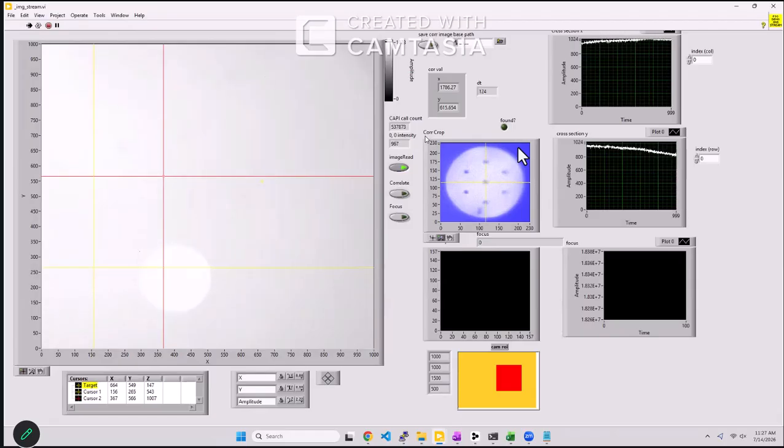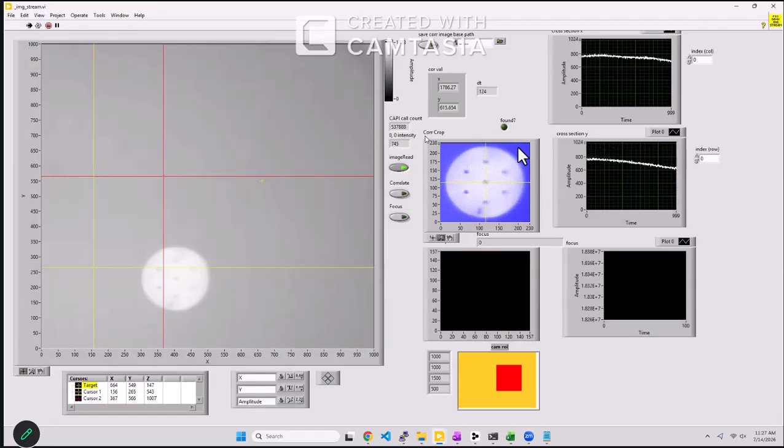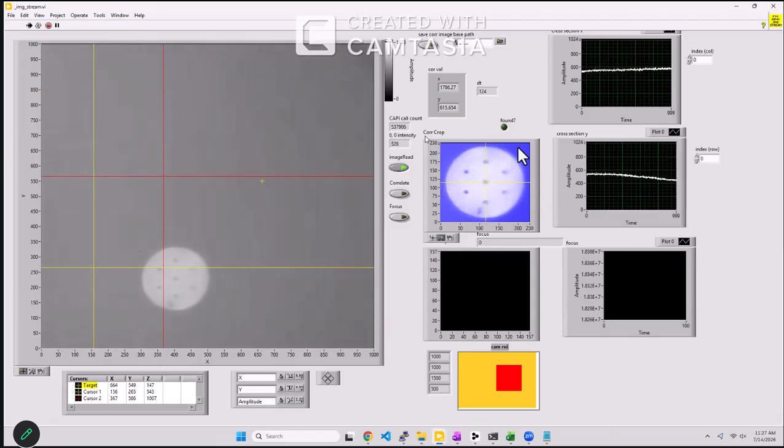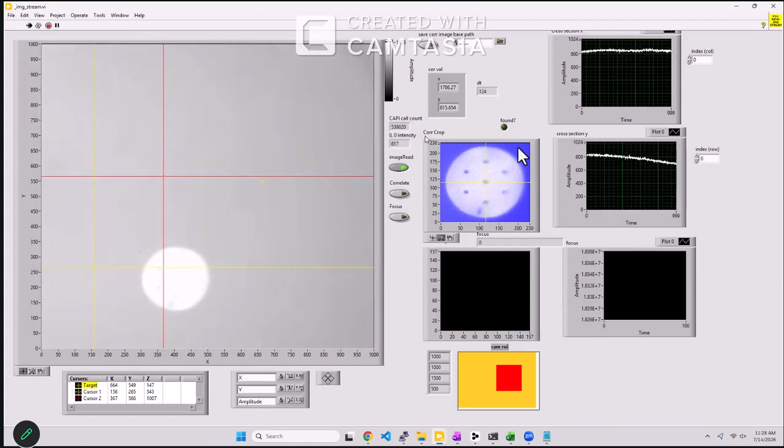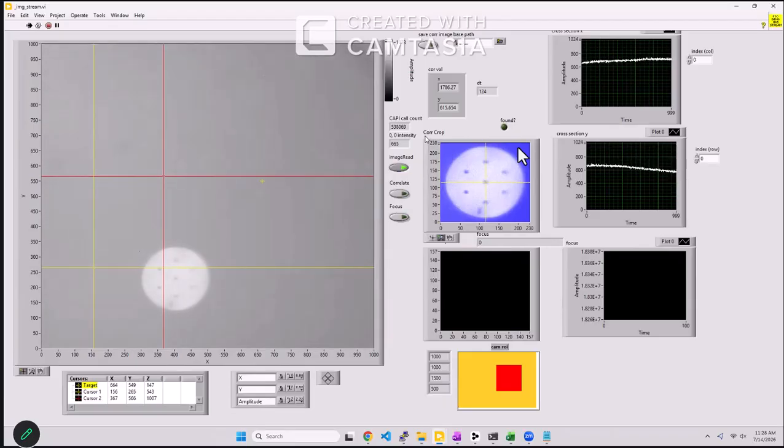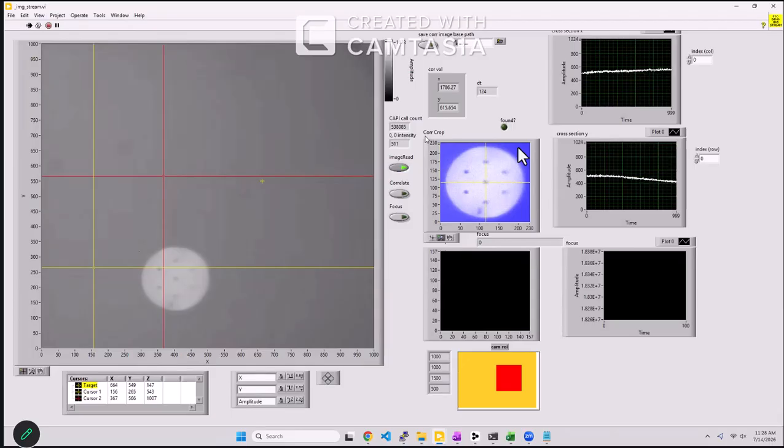And that's the sensor that we'll use to get our reference image. Because the image sensor is fixed relative to the other system, every time you put a different shape sensor on it, do you need to recalibrate? No. Once you put a different shape sensor on it, like a different catheter, as long as you drive it to that predetermined calibrated reference image position, it's more or less very close.